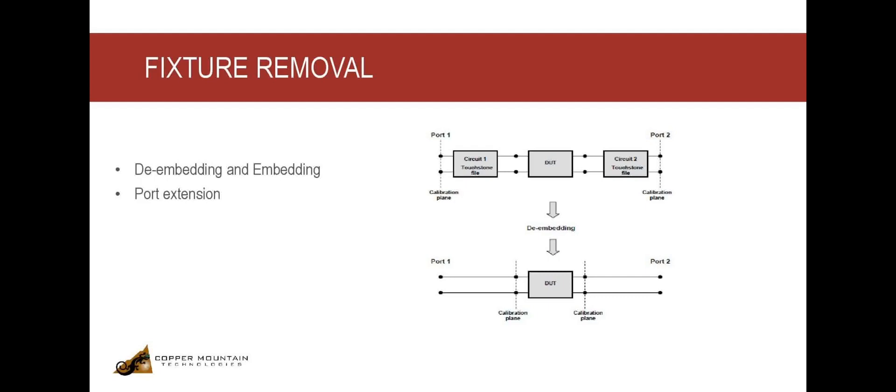But these days, there is also an auto port extension function available, which allows for automatic calculation of port extension parameters by measuring short or an open standard. The result of the auto port extension function is actually the calculation of the electrical delay value.